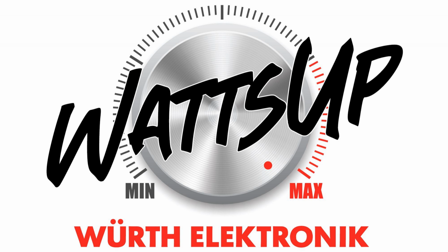So the rated current is defined for 55 Kelvin self-heating. And so I have to reduce it if I go above the 70 degrees. The reduction is not done linearly. Instead, it's a nonlinear behavior, which you will see on the next slide. So there's slightly a margin or a buffer which you have for the rated current. So this is valid for mains filter chokes.